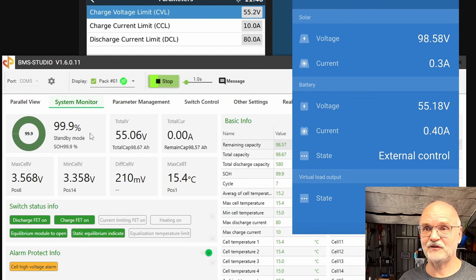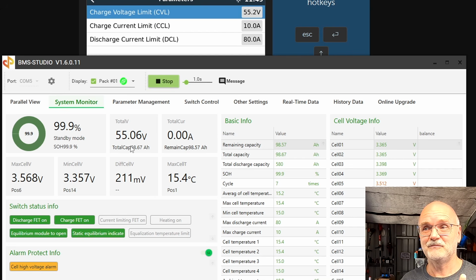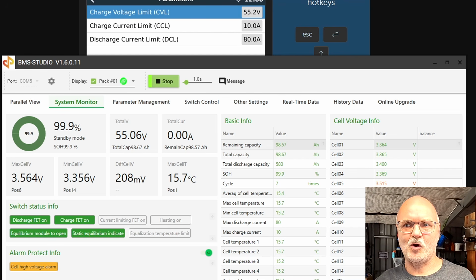As we can see, the battery has fully absorbed now. We are charging with 400 milliamps into this pack, and the voltage will come up a tiny bit. I have seen 55.09, but it takes hours to reach that because the charging current is so small now, which is perfect because we are balancing, right? We don't want a high charge current while balancing. Balancing means we are taking energy away from the high voltage cells. So the battery is basically absorbed now, it's just waiting for the reset to 100%.